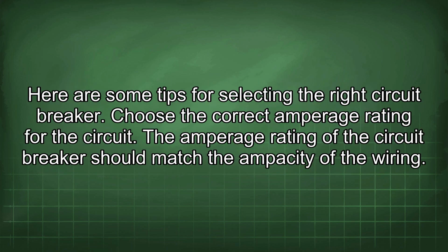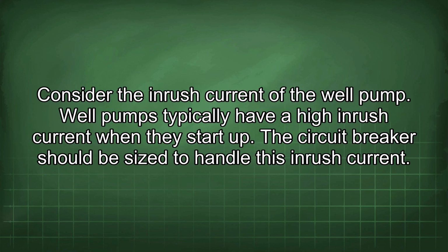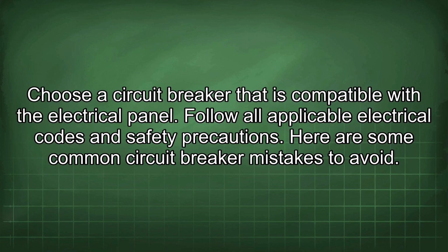Here are some tips for selecting the right circuit breaker. Choose the correct amperage rating for the circuit. The amperage rating of the circuit breaker should match the ampacity of the wiring. Consider the inrush current of the well pump. Well pumps typically have a high inrush current when they start up. The circuit breaker should be sized to handle this inrush current. Choose a circuit breaker that is compatible with the electrical panel. Follow all applicable electrical codes and safety precautions.